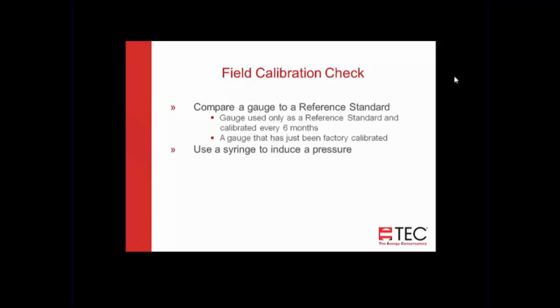And you're going to use a syringe to induce a pressure and do the check at a number of different pressures, but you want to make sure not to damage the sensor with that syringe. Larger syringes can easily overpressurize the gauge, and then you're going to have to send it in for calibration and repair. So the way to make sure you're not damaging the gauge is if you've got an old Magnehelic gauge around, or you could certainly buy a new one also, and you can use that as a buffer. It's got a bladder in there that'll protect your gauge from overpressurization.